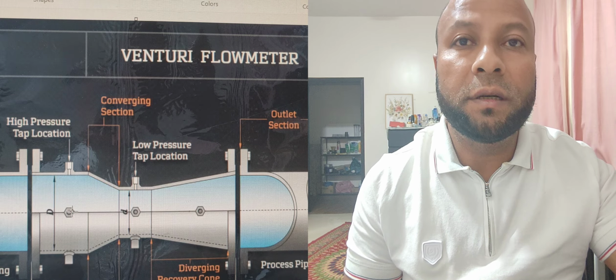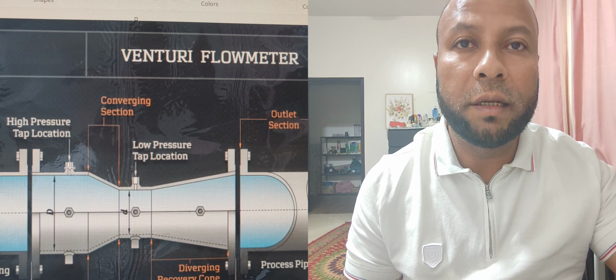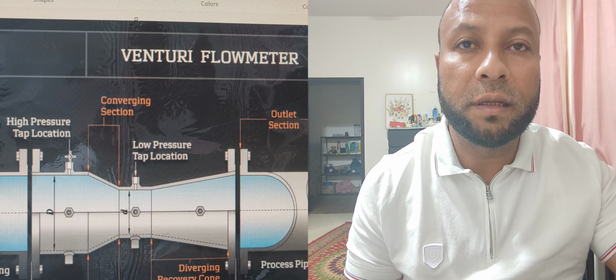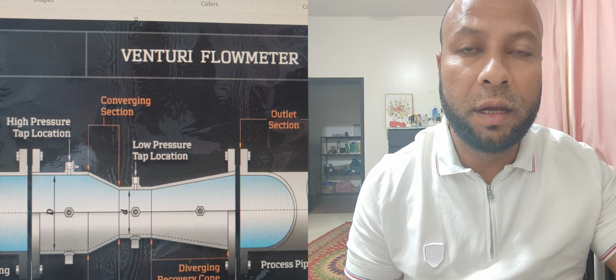That was the case that created the deviation and difference between the A and B transmitters. They should be similar, but the pressure from the high tapping point and its root valve was affected by the sticky material inside the pipe and the needle valve.